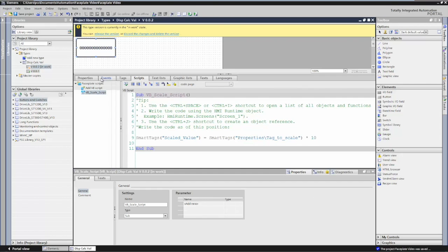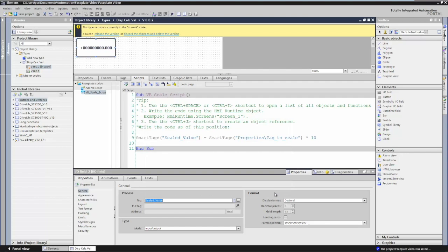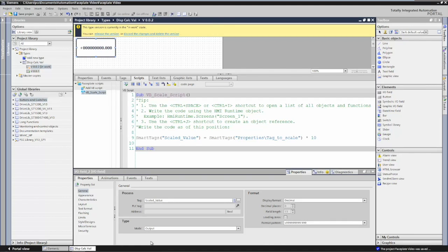The next thing I need to do is go to the properties of my IO field, and the scaled value tag is going to contain the scaled value. I'm going to assign that to the IO field, so now this IO field will display the scaled value. For the type here, it's not going to be an input/output — it's only going to be a display, so I'll change the type to output.